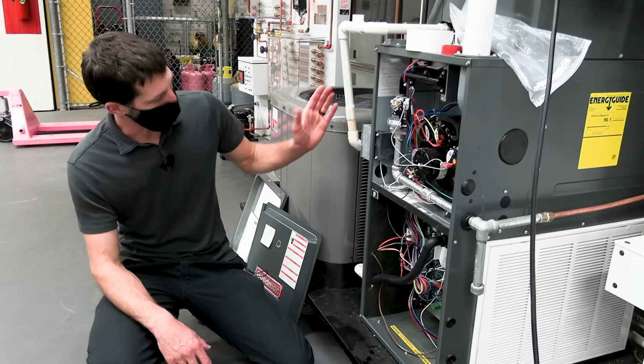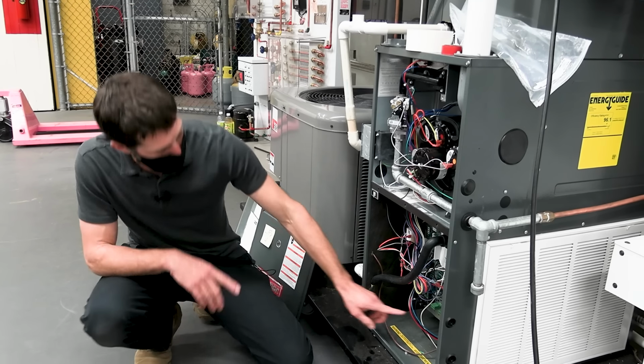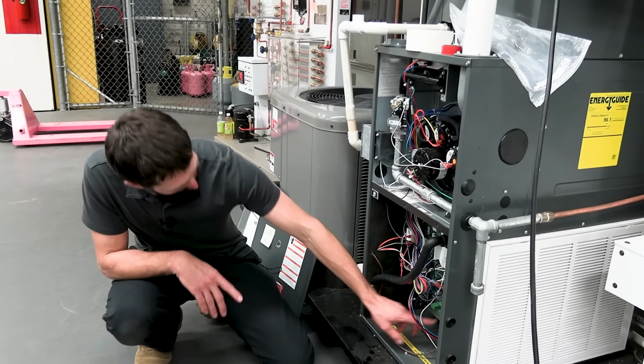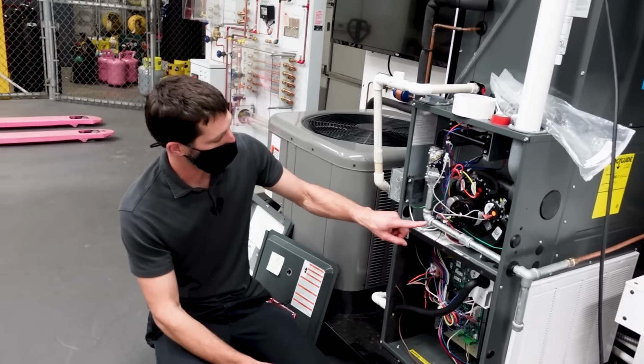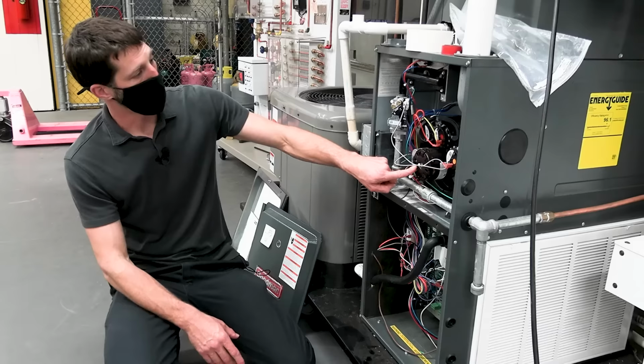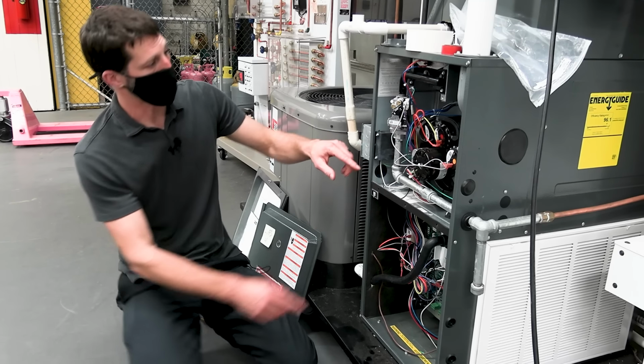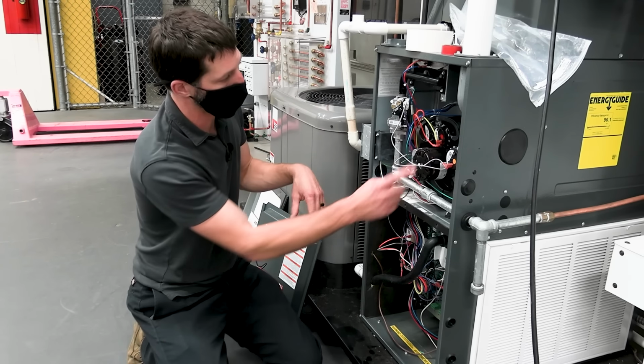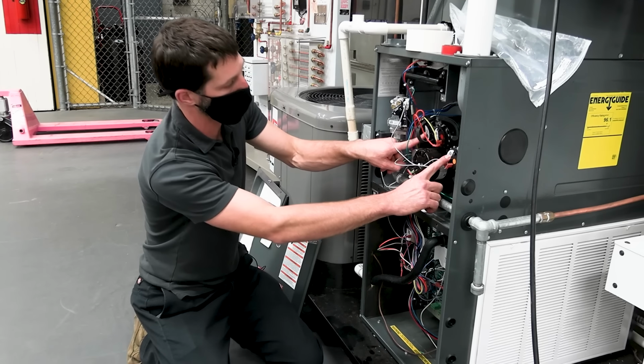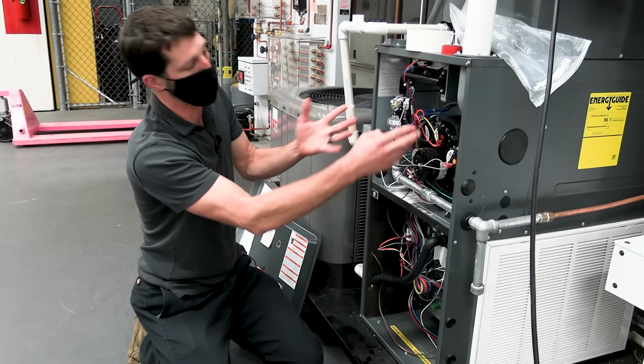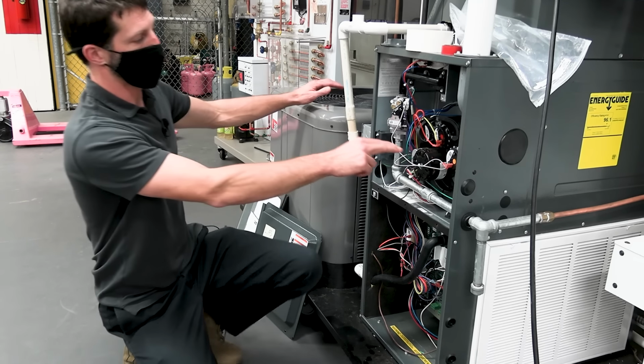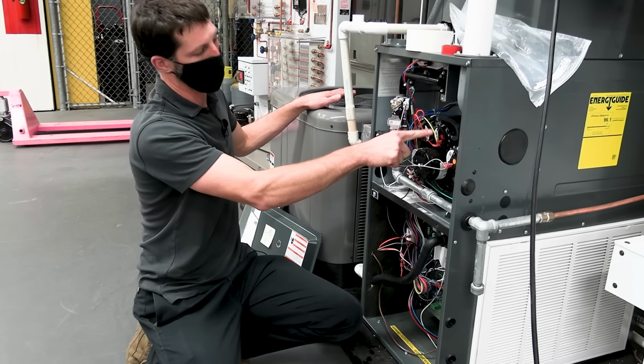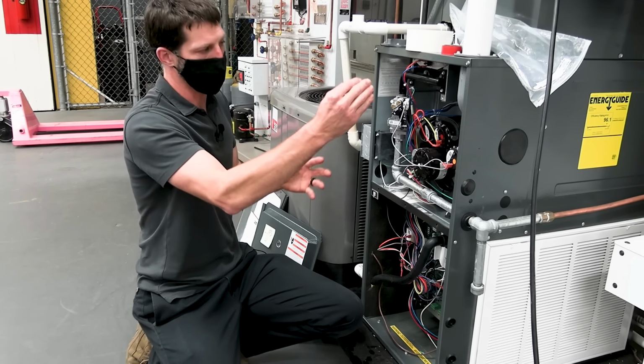So anyway, on a call for heat, R and W touch, and so once you have 24 volts on the W here, it starts the sequence of operation for heat, where the inducer motor turns on first, and then the pressure switch is closed, at least, so say it's in low speed, this switch and the low speed switch are going to close. This one may still be open, but it's probably going to close as well, because the inducer motor pressure is going to be higher than these. It's not going to be closed. It's going to be a significant amount higher.